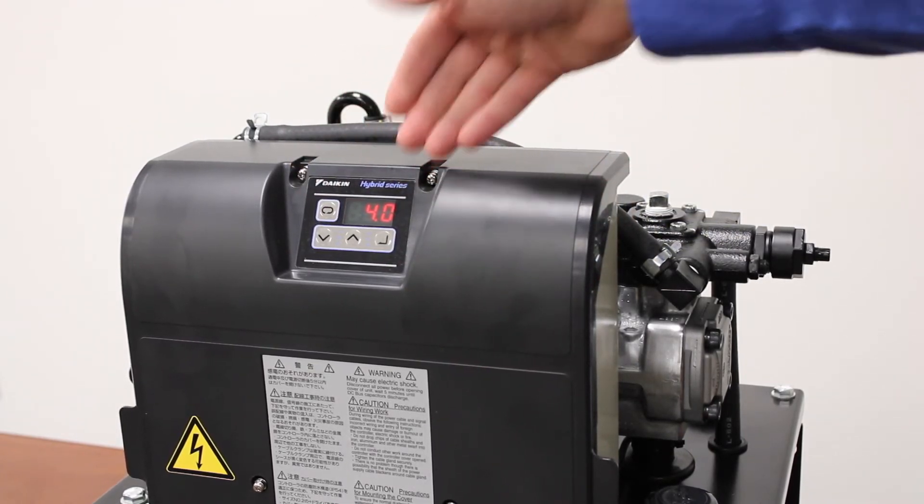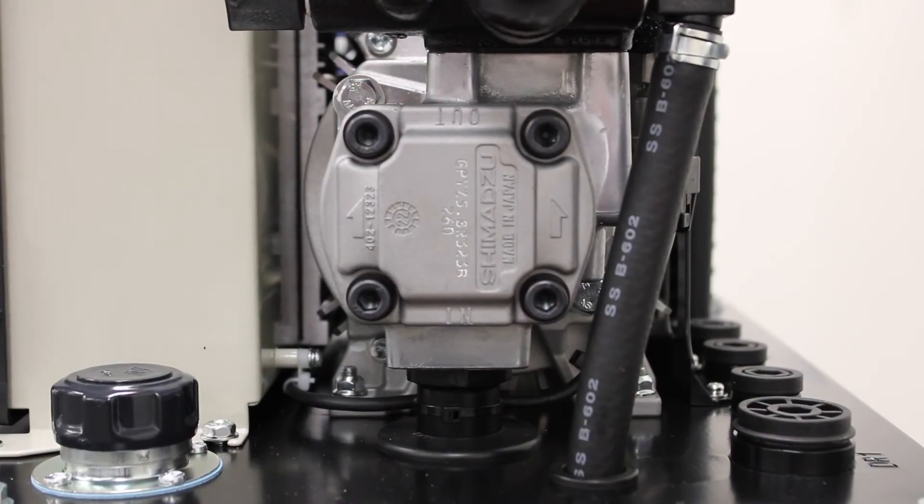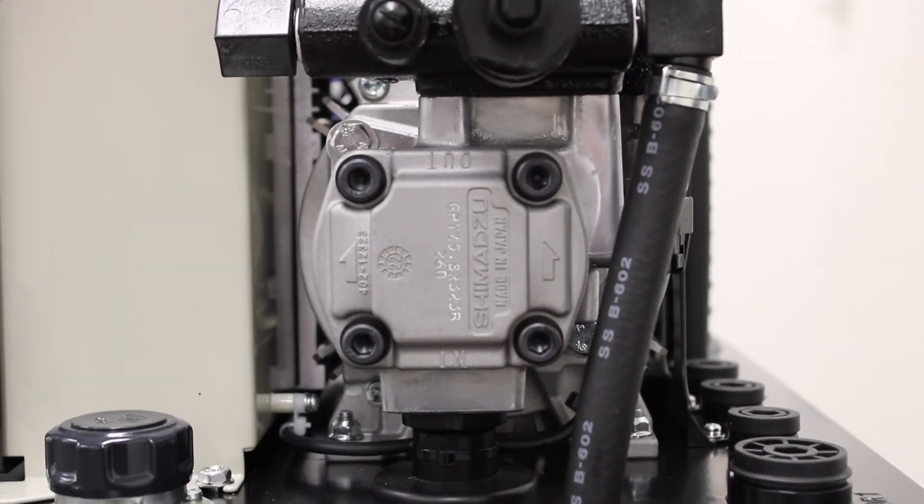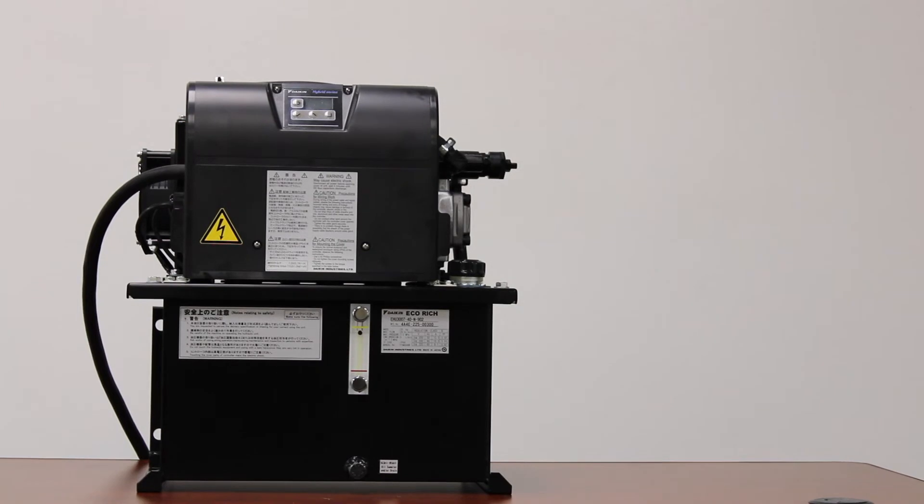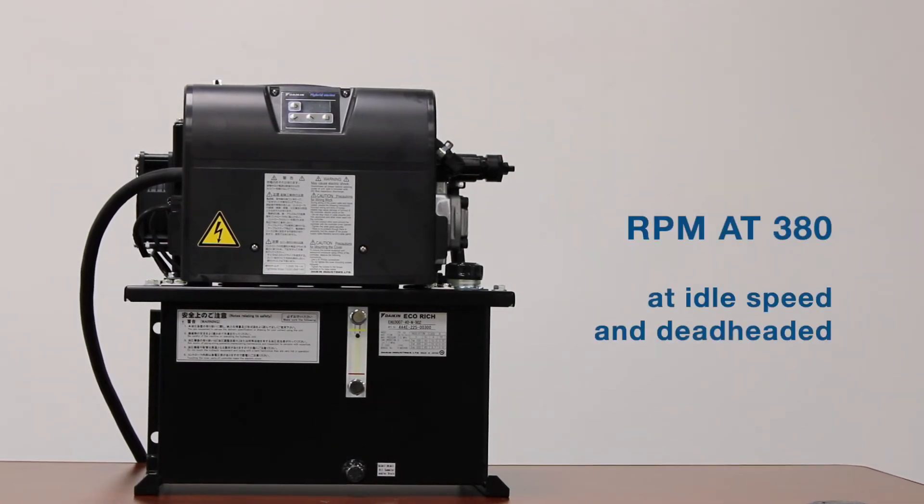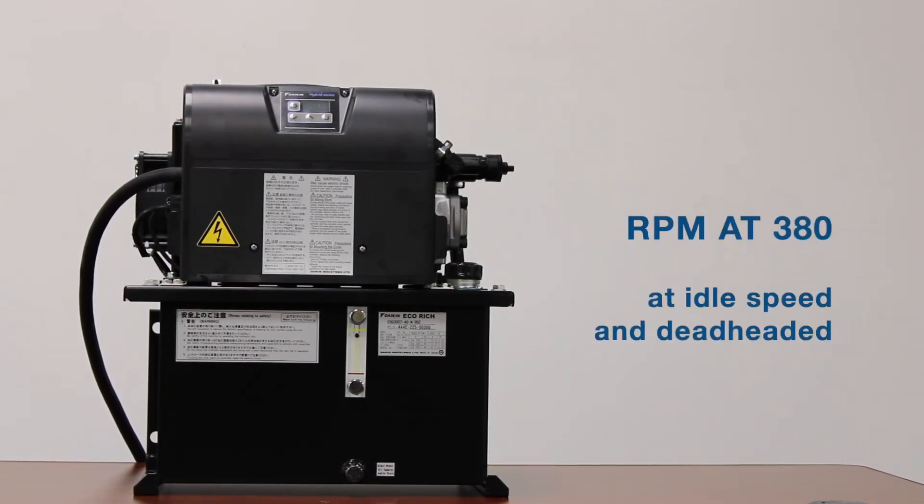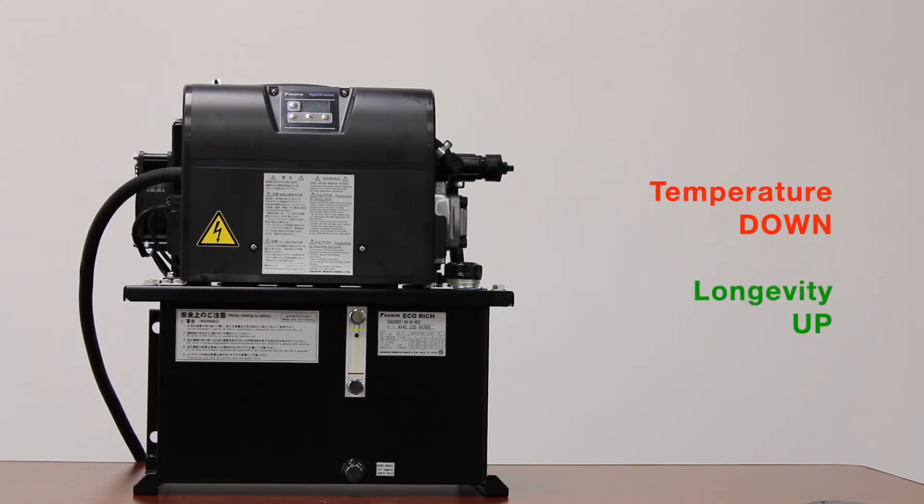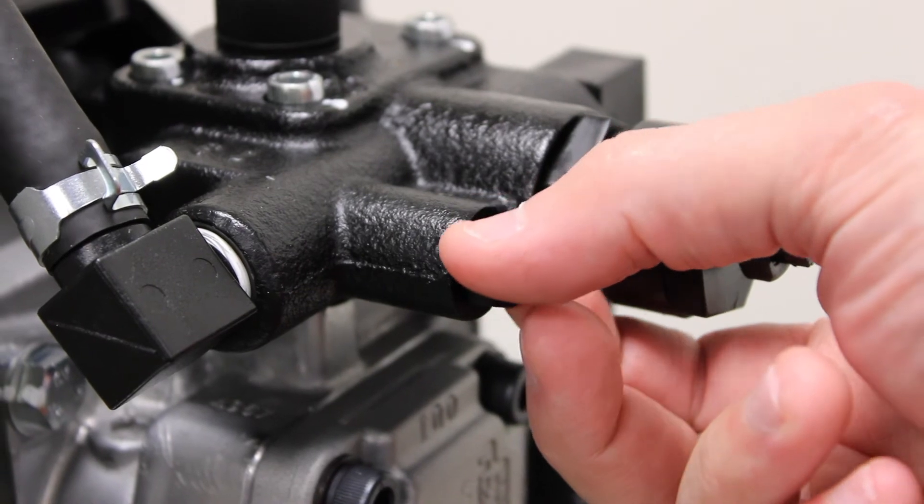Once you've made these changes, we can push the menu key and then it should go back to displaying your set pressure. After we've set our pressure and our flow, it's important we set the motor RPM. We want to keep the motor RPM around 380 when we're at an idle speed and the pump deadheaded to keep the temperature down and increase the longevity of this unit.